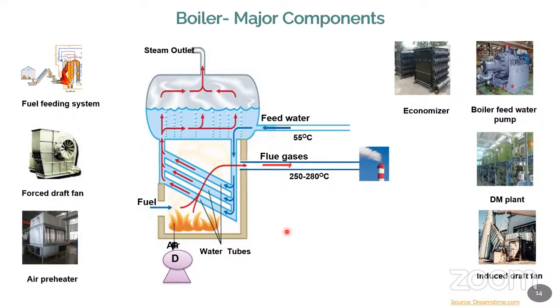Suppose they are using firewood, what will happen to the firewood? Normally the firewood should be pulverized. It should be cut and should have a greater amount of pulverization. But 99% of the industries are not using pulverization techniques. They don't even cut the wood and put it in the fire chamber. They put the complete piece of wood into the chamber, and it will take more time to reach the temperature.